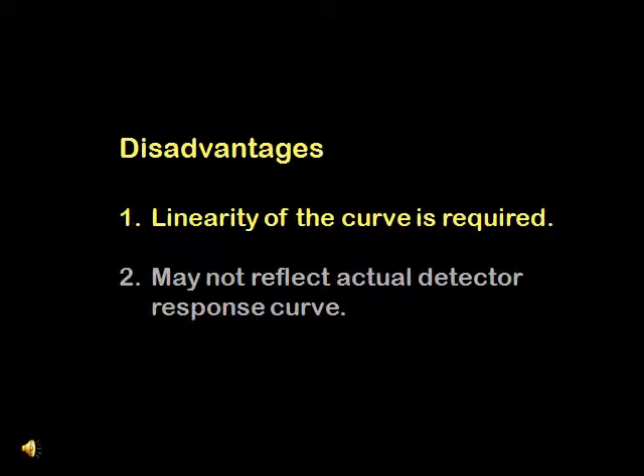Some of the cons to using the calibration response factor calibration is that the curve must be linear, and the actual detector response factor may not be properly reflected.